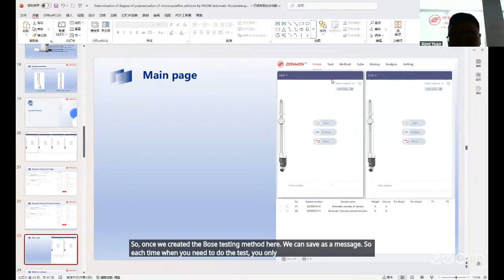So once we have created both testing methods here, we can save them as methods. Each time you need to do a test, you only select the method from here directly. For example, in this page, you can see we have selected the kinematic viscosity of the sample, and the second method is the kinematic viscosity of the solvent. So you don't need to write it every day, you just choose it directly and click start. Once we create the method here, it will be saved here, so you can use it from the main page directly. So this is the automatic testing of kinematic viscosity.